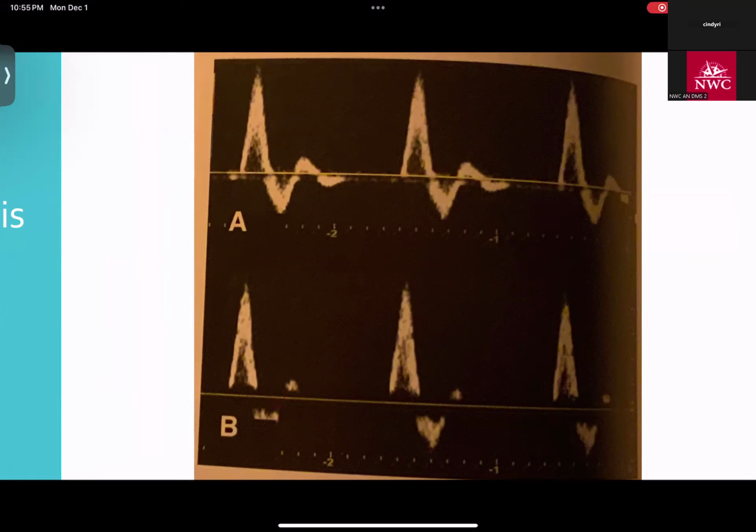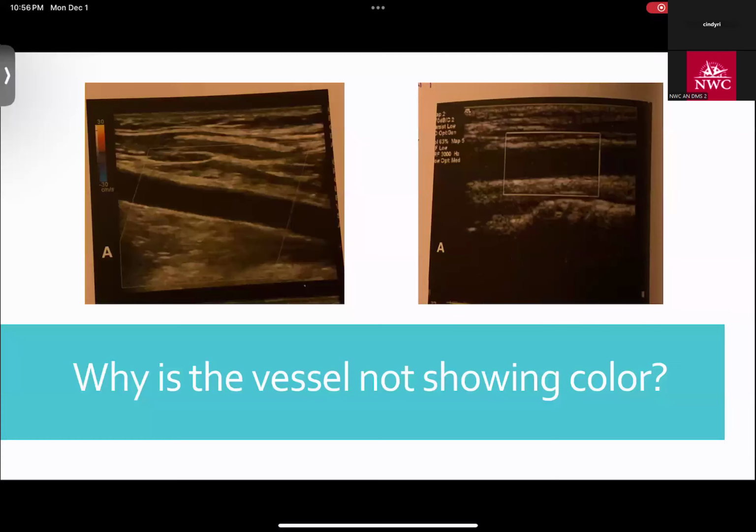Therefore, which button is being used to eliminate those lower frequency echoes that are around the baseline from A to B? So if you said high pass filter, you are correct. Wall thump filter. Here are two more examples of what they can show you.